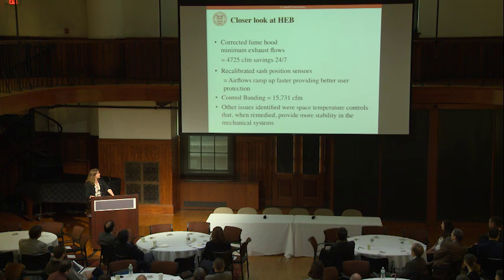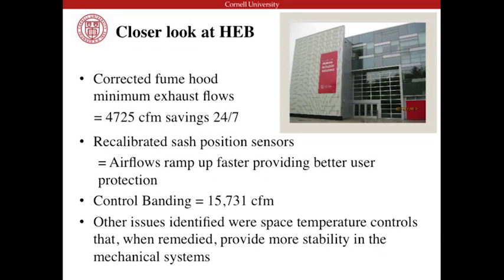Through the control banding, we ended up saving almost 16,000 cubic feet per minute. We also corrected the minimum exhaust flows for the fume hoods, which found some savings. And then there were just other issues.